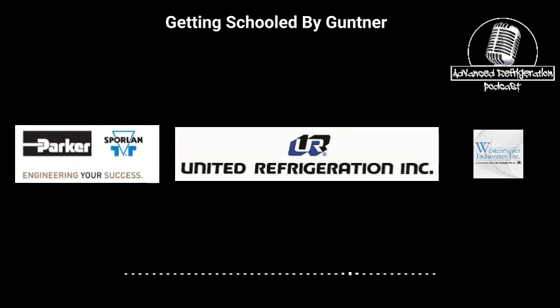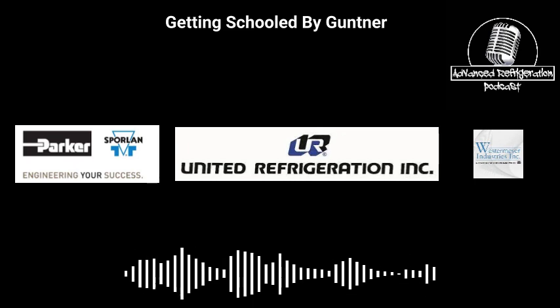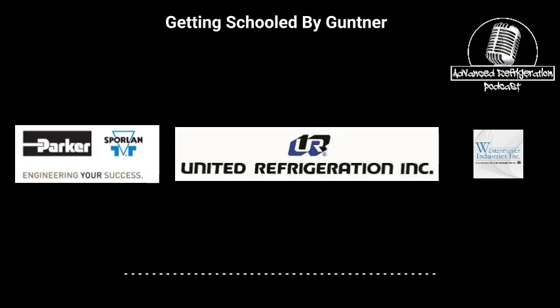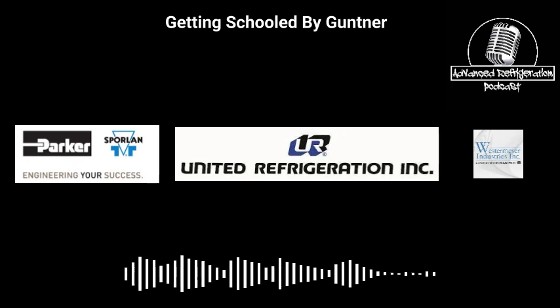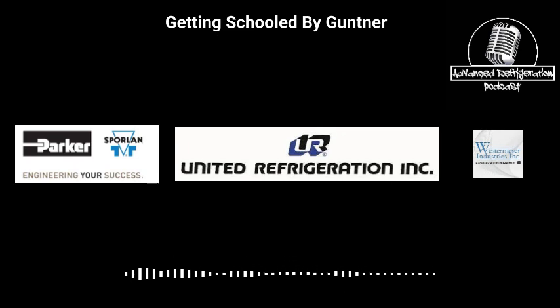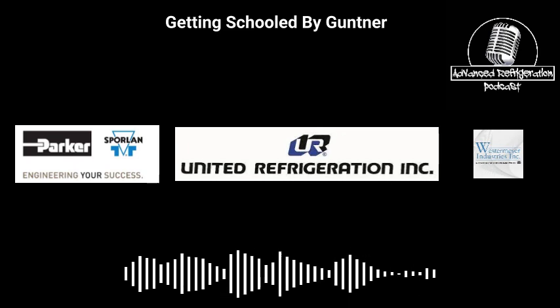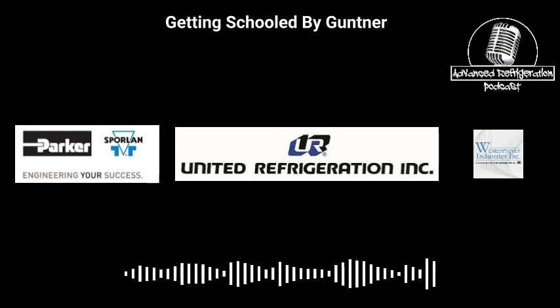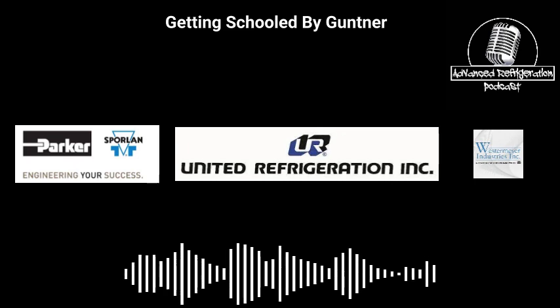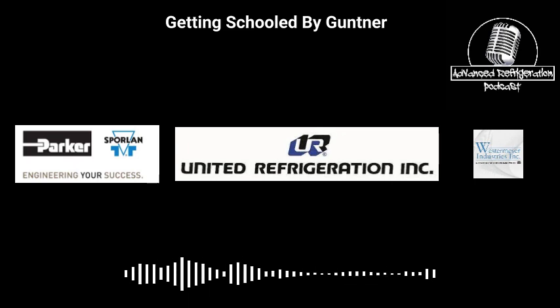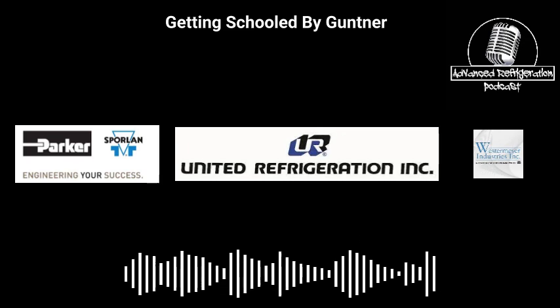No addressing necessary. We also have a maintenance run feature, which some sites use, especially in the winter. Up here in Chicago, it's cold. This January, it's not that cold, but it normally gets really cold. And they will shut down the unit come January and not start it up until March. Our fans are designed to run, because if you shut a unit down and don't let it run, the bearings on the fans can flatten, and condensation can form inside the electrical terminal box and cause damage to the fans.